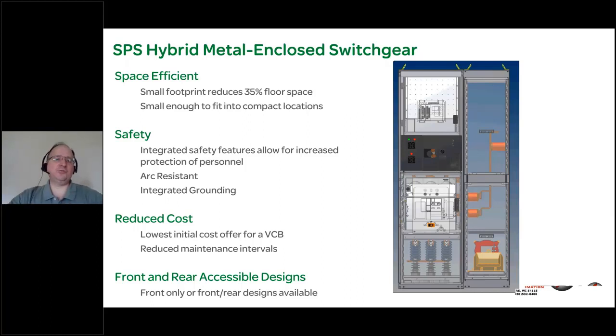This hybrid metal-enclosed switchgear is highly efficient; the footprint itself is 35% less than you would typically find in a metal-clad switchgear design, and it has a number of integrated safety features for increased personnel protection. First, we have an option for active arc quenching. I'll cover that; this is not an arc quenching presentation, but the bottom line is that via installation of the arc quencher device and system, we guarantee, both in the switchgear and in downstream assets protected by the light sensor network, less than 1.2 calories per centimeter squared at the IEEE 1584 working distance, which for this equipment would be 36 inches.